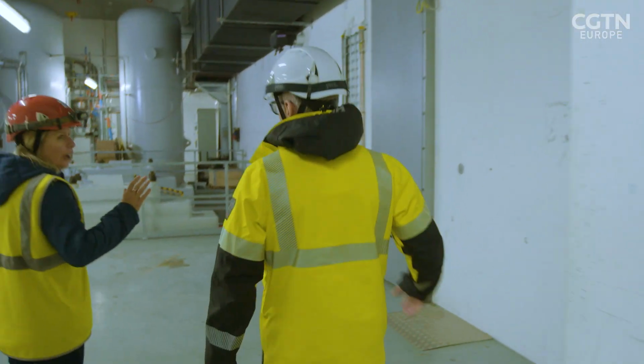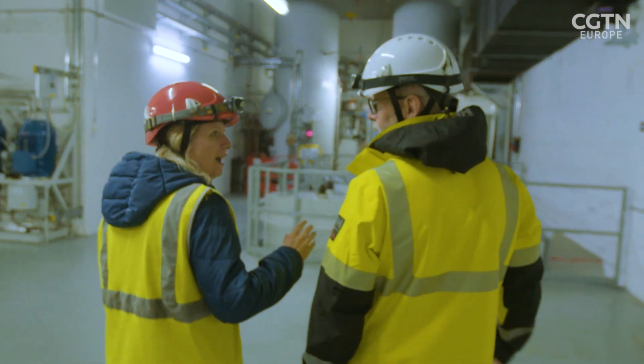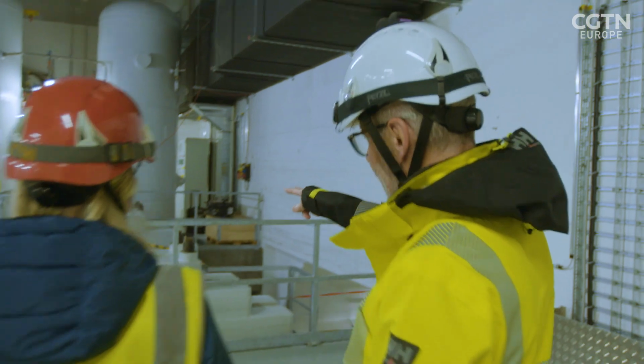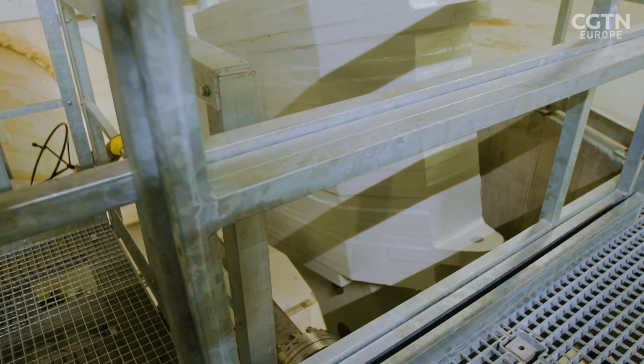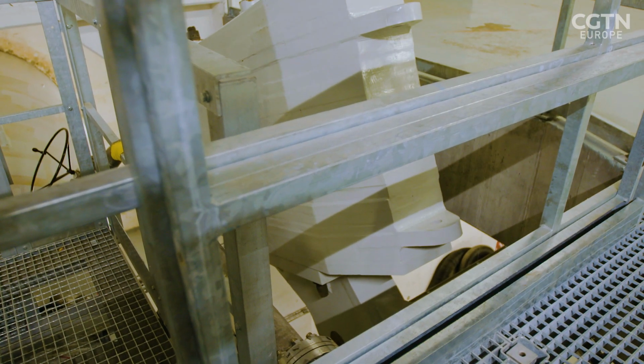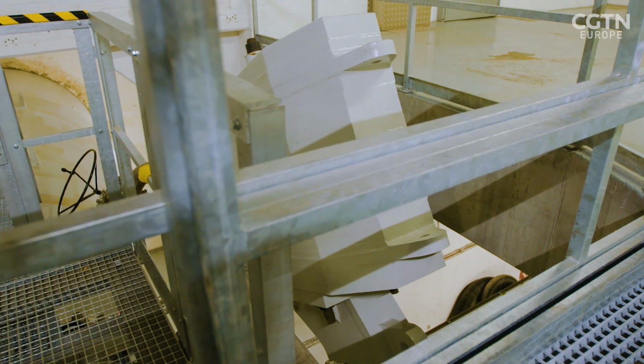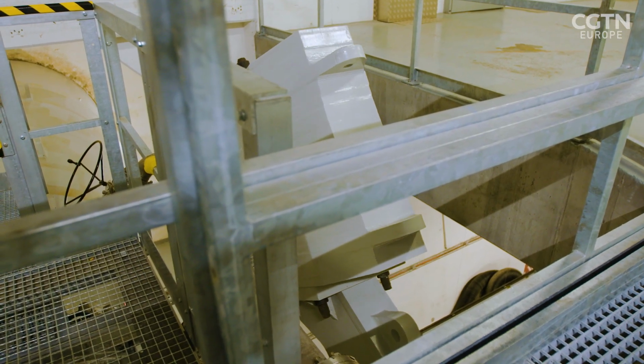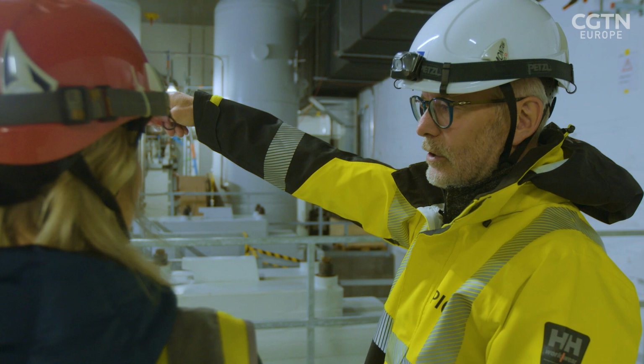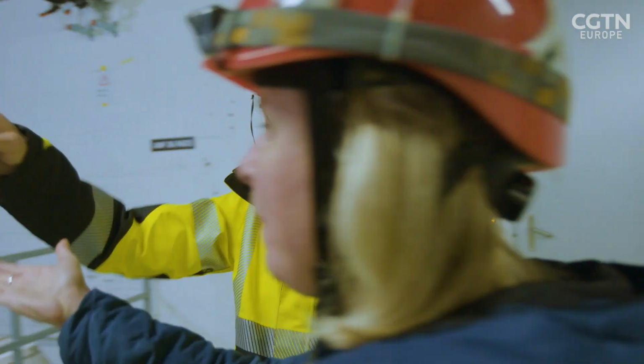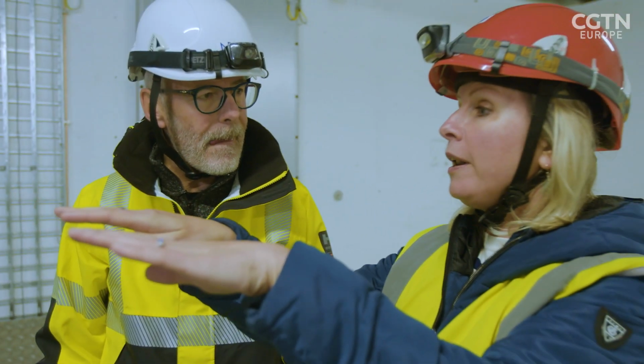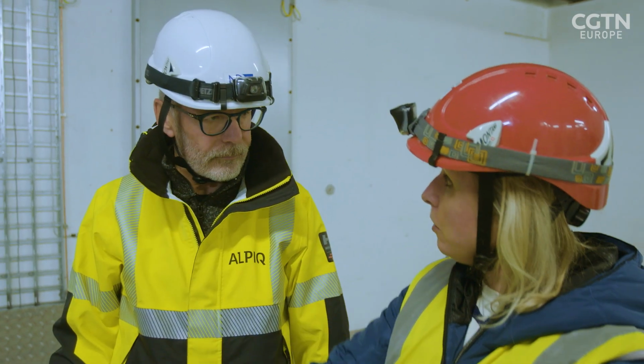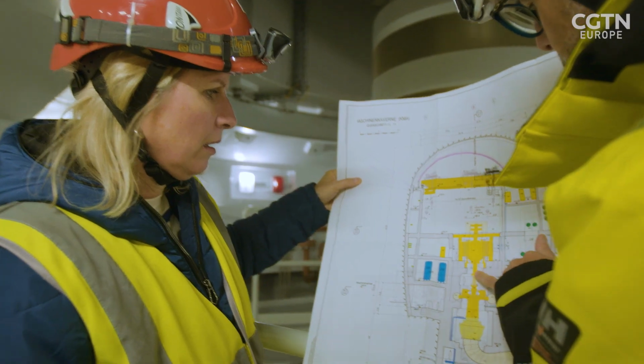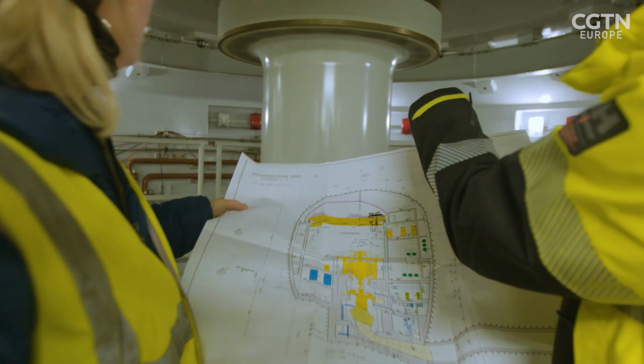Next stop, level -2. Oh, wow. Obviously, the machine is in operation and we can hear it. But another sign is that the counterweights of these spherical valves are up. It means the valve is open. The water can flow through the valve and go inside the turbine. So the valve is open, the weights come up, and when it's time to close the valve, the weights go down. Yeah, exactly. So this shaft is what we see turning.